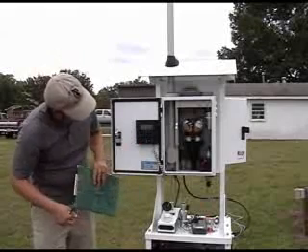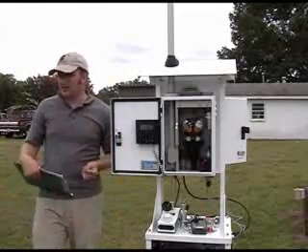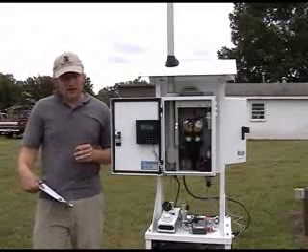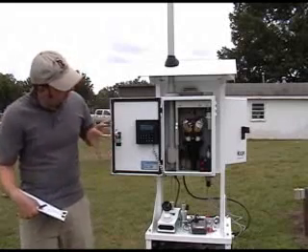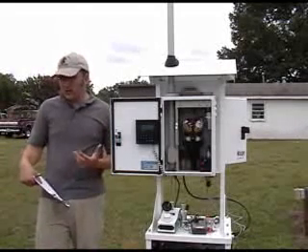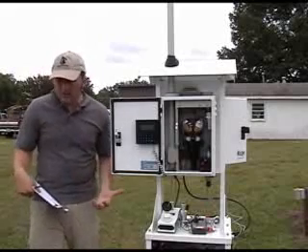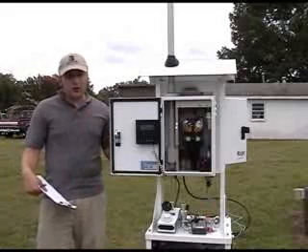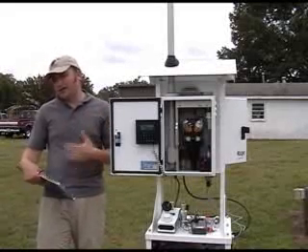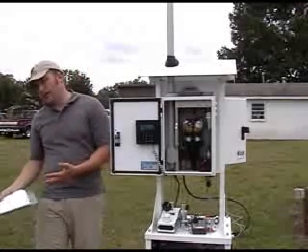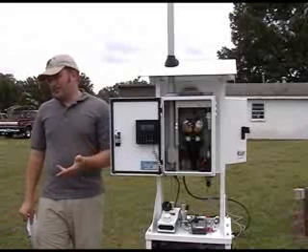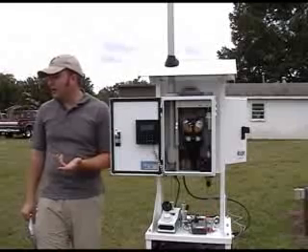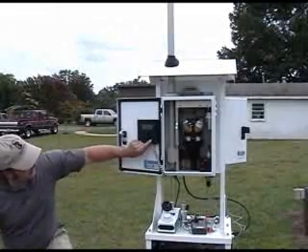And lastly, sample time per hour. This is the duty cycle of the instrument. Right now it's going to be set up to run 60 minutes of every hour for the entire sample day. The only reason why you might want to consider changing this is if this was a heavily polluted site where you get heavy filter loading, which would cause your flow to drop, and eventually that would invalidate the sample because you wouldn't get an appropriate size cut any longer. You could change it so it would only run 50 or 40 minutes of every hour. So on the startup day, it'd run 40 minutes, off 20, run 40, off 20. But you'd lose the sample anyway because you would violate the 24 plus or minus 1 hour of sampling. So 60 minutes, we'll leave it at 60.